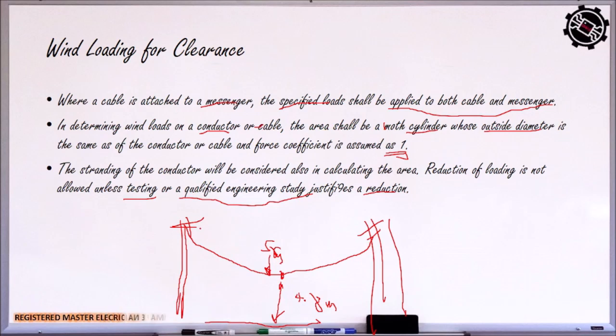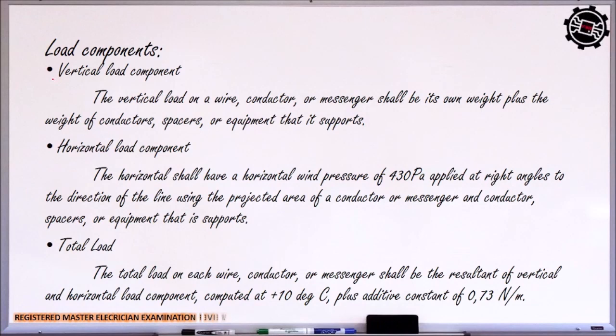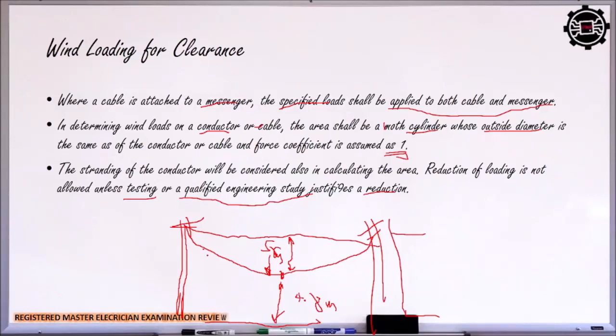Kasi nangyari din yan in the computation, they will also assume na kunyari walang sag dito. Yan. Meron kang length din dito. Tapos yung total length mo from the highest point to the surface of the road, minus mo dito, so yan yung magiging clearance mo, which is not below 4.8 meters. So vertical load components tayo. So these are the components, no, ng ating gagamitin in order to design for the sag, para makuha yung sag ng ating cable, no. So vertical, so yung vertical load component, so balikan natin yung drawing natin kanina. So yung vertical load component, ito yung load na pababa. Yan.